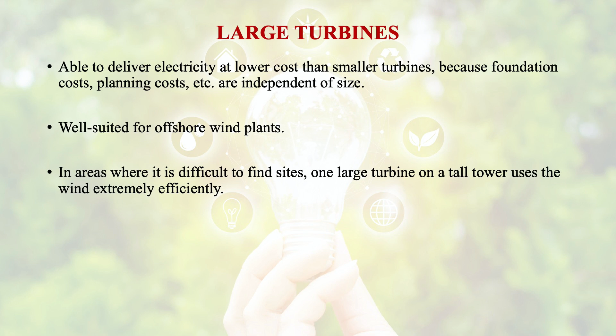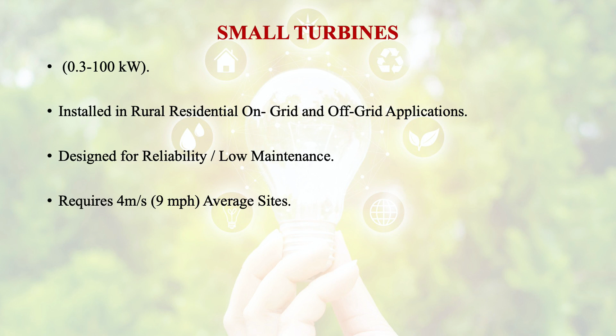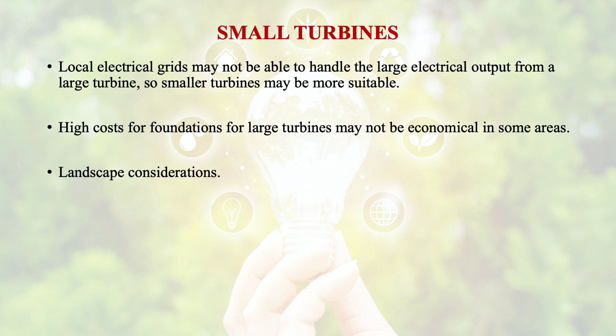If we talk about the small turbines for 0.3 to 100 kilowatt power generation, as we discussed, these are installed in rural residential areas for on-grid and off-grid applications. These are designed for reliability and have low maintenance. The wind speed required for these turbines is 4 meters per second or 9 miles per hour. Local electrical grids may not be able to handle the large electrical output from a large turbine, so smaller turbines may be more suitable in that case. High cost of foundations for large turbines may not be economical in some areas, and we could consider the landscape considerations as well for small turbine applications.